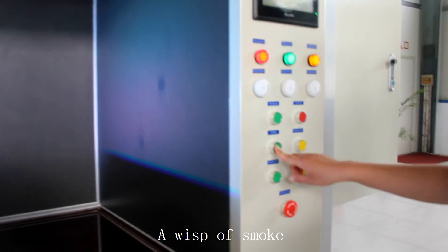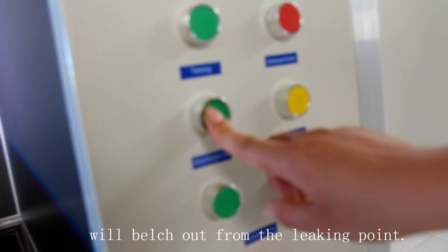If there is a leaking point in the filter, a wisp of smoke will emerge from the leaking point. Then use a pen to mark it.